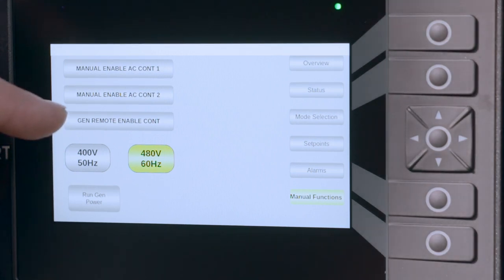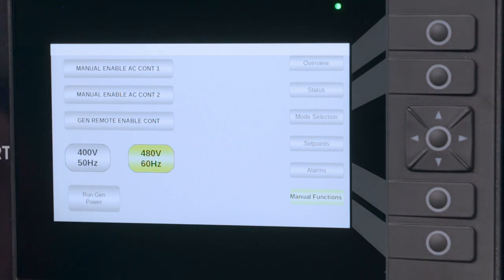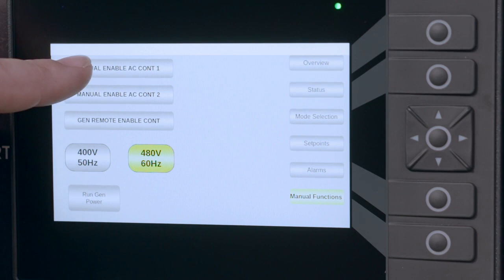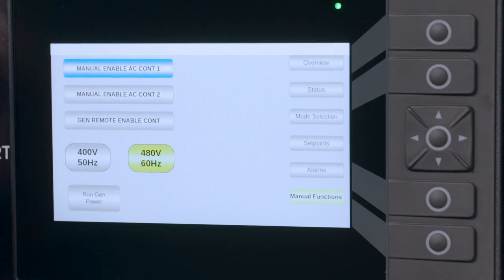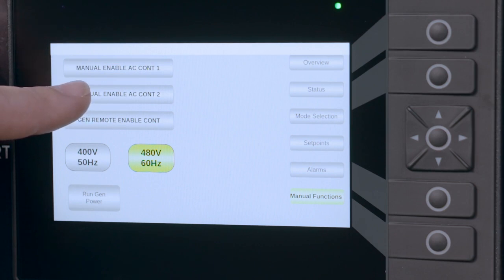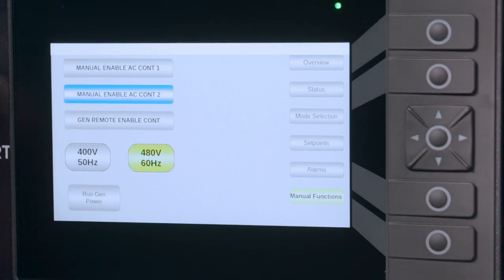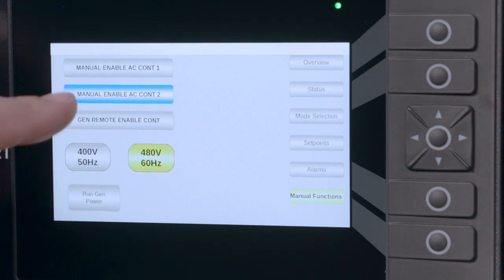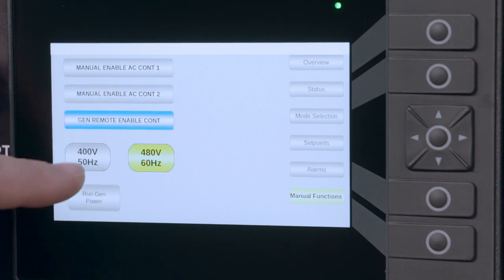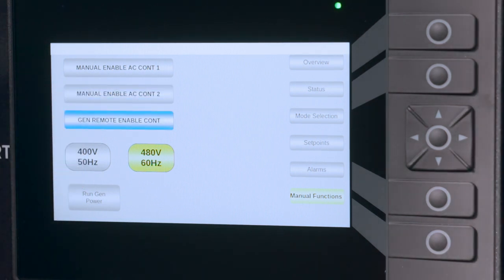The manual function screen will allow you to test and make sure that contactors are working as they should be. Manual enable contactor 1 will pull in your cam and allow power flow to your load grid cam locks. Manual enable contactor 2 will allow power flow through your auxiliary generator cam locks. And generator remote enable contactor will pull in the dry contact to send the start signal to the remote generator.